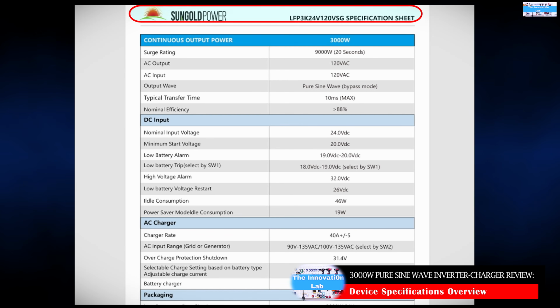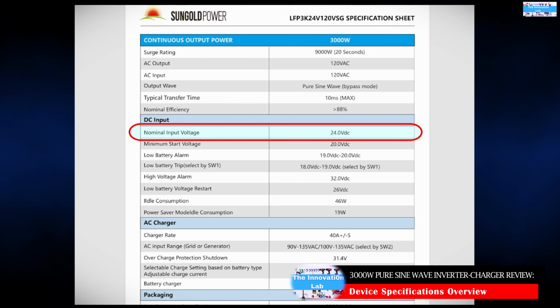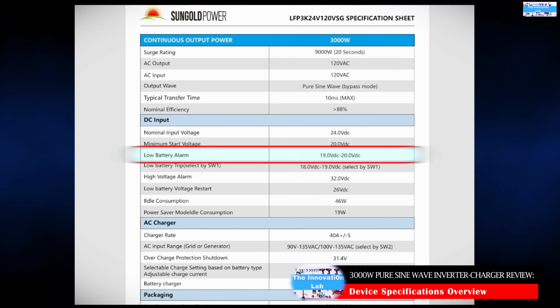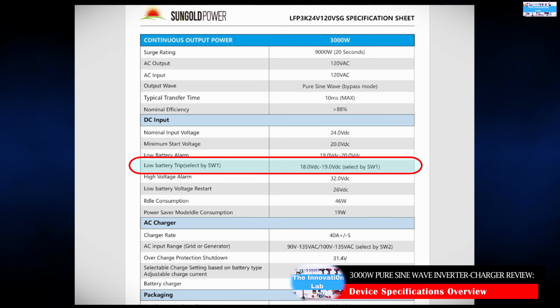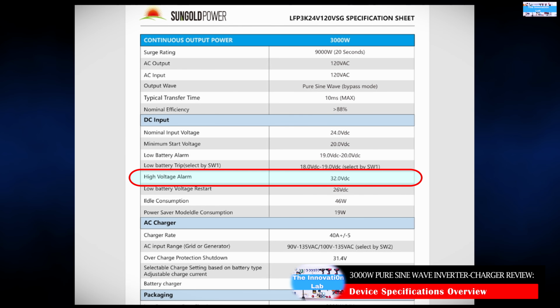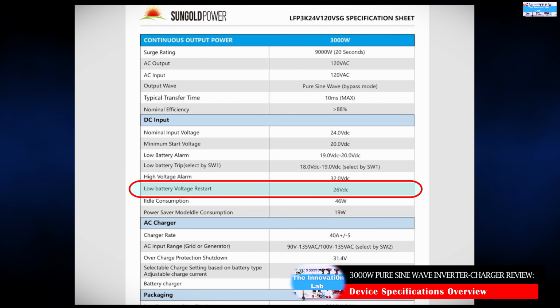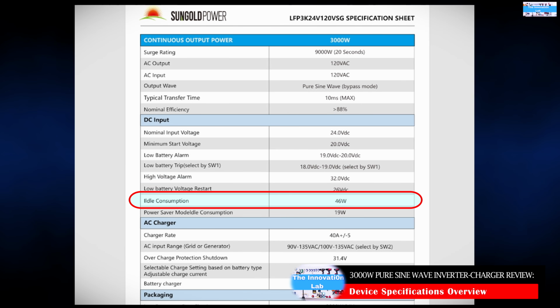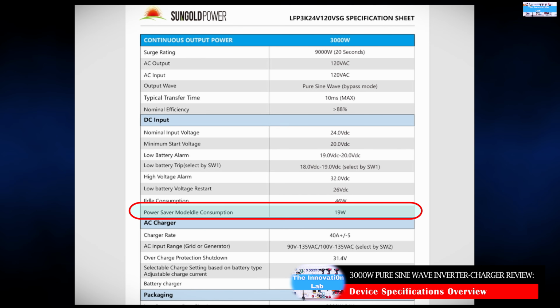On the DC input side, the nominal input voltage is 24 volts with a minimum start voltage of 20 volts, a low battery alarm range of 19 to 20 volts, a low battery trip (if set to switch 1) of 18 to 19 volts, a high voltage alarm of 32 volts, low battery voltage restart of 26 volts, idle consumption of 46 watts, which you'll see when we conduct the idle or quiescent power measurement, and a power saving mode consumption of 19 watts.